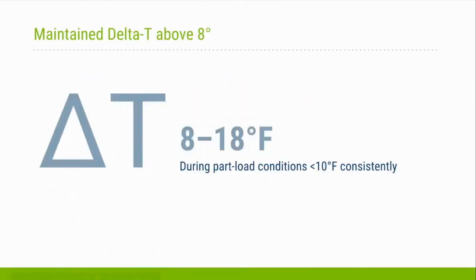The number one thing that we saw based on the data and the measurement and verification was that the delta T was consistently maintained above 8 to 10 degrees. I apologize for the wording there. During part load conditions, that should say greater than 10 degrees Fahrenheit consistently, 8 to 10 degrees. The delta T was noted as being as high as 18 degrees. So there's a lot of improvement.